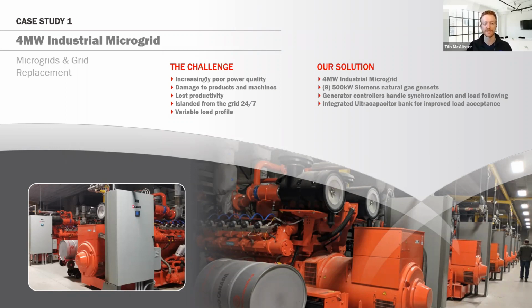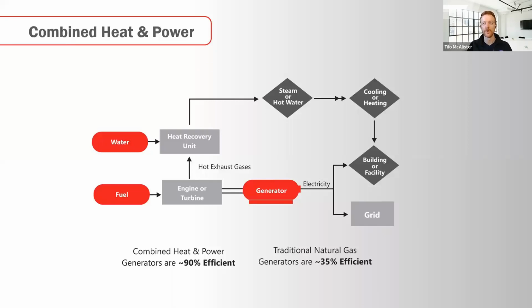That brings us to our next application, where we're taking the efficiency of this system from somewhere around 35% up to 90% or more by capturing all that thermal energy. We can put a heat exchanger on the hydronic coolant loop of the generator, and a heat exchanger on the exhaust, and recover most of that energy as hot water or steam. With recip generators, usually we're going for hot water.